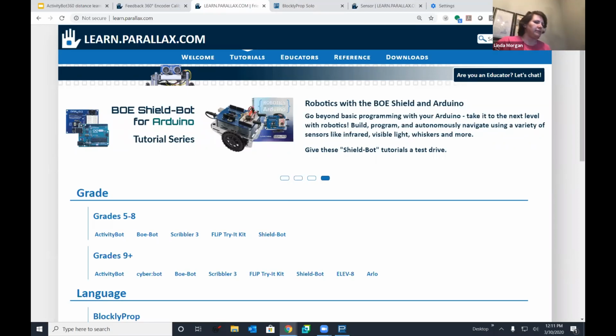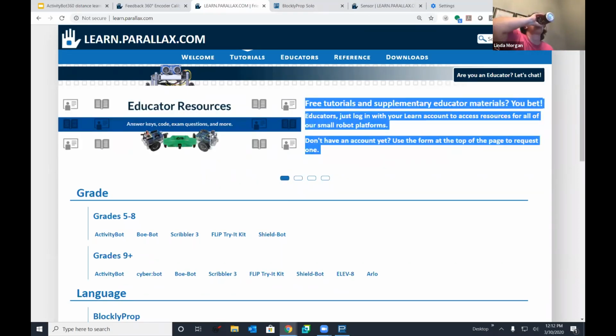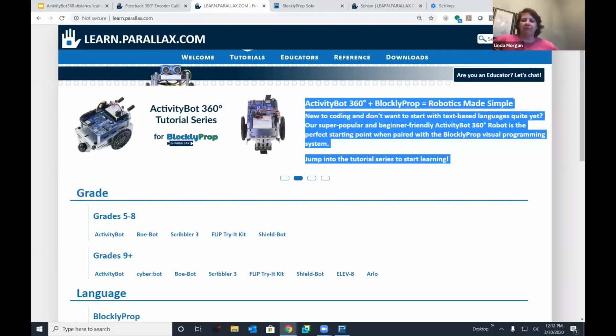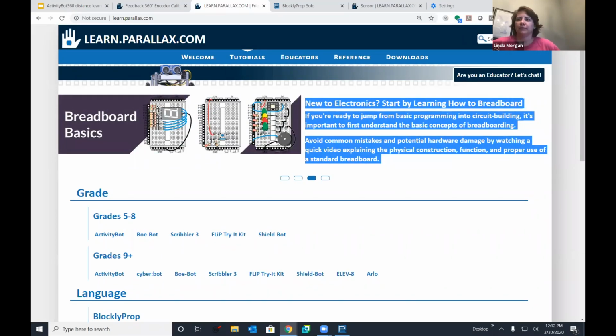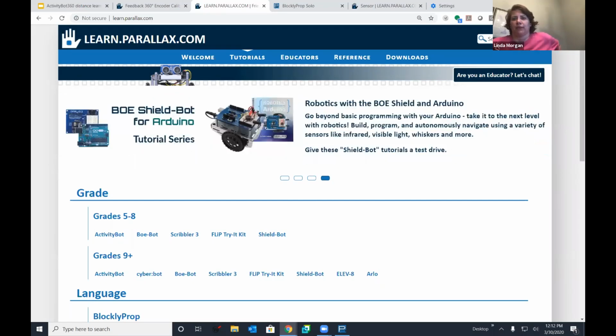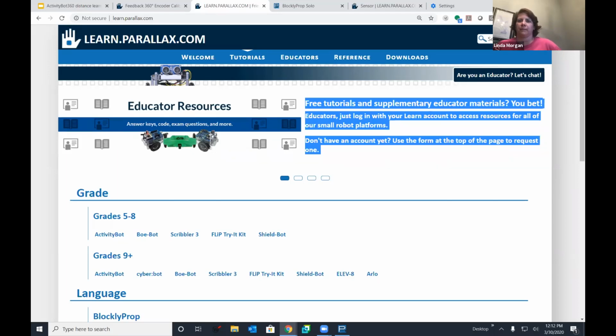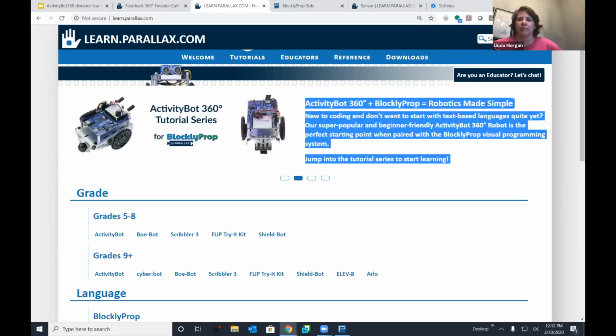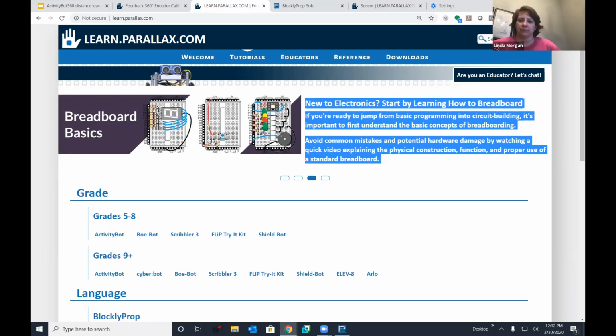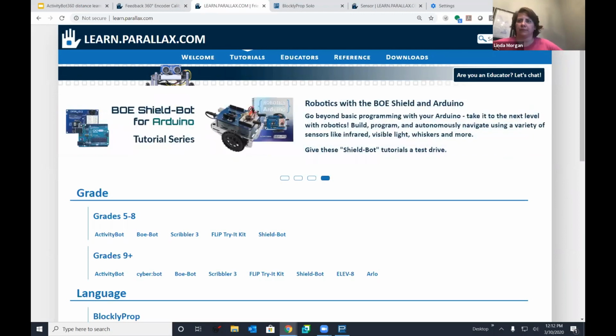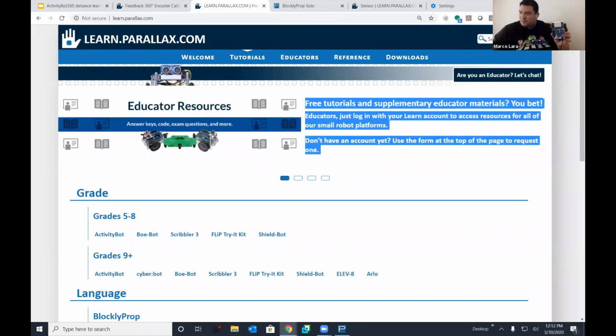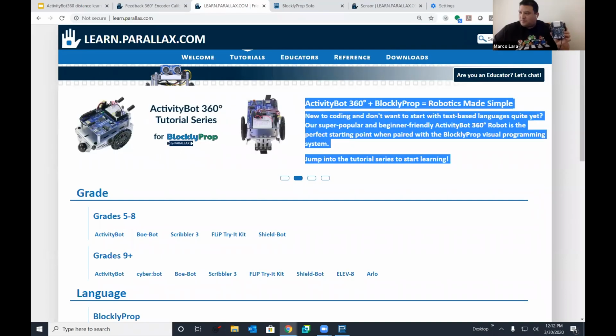Yeah, it wiggled most of the time. A couple times I did get it to do something else other than wiggle, but not consistently, not two times in a row. Andy, you ever seen that? No. Usually, if there's something wrong, it'll wiggle, and if there's something right, the yellow lights just turn off. So if something's wrong, it'll wiggle and the yellow lights will flicker. If something's right, the yellow lights will just turn off. And essentially, if they do that after it's done its maneuvers, then we don't have to repeat the calibration.